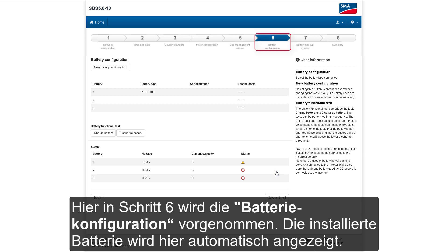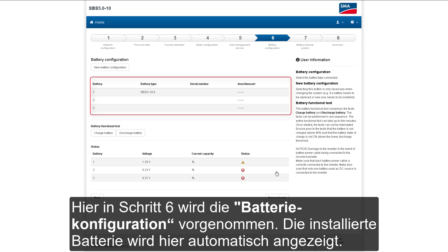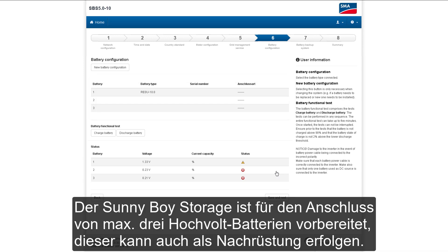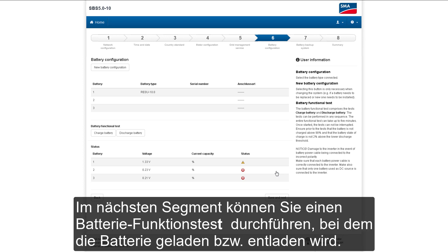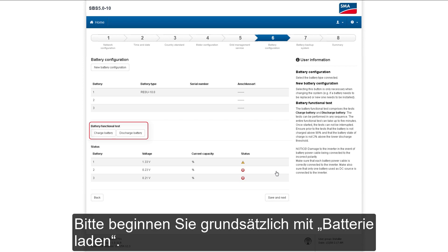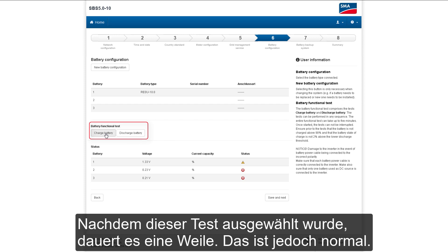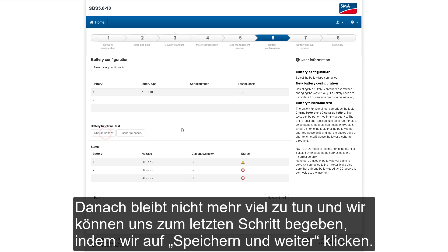At step six, we can set the battery configuration. The installed battery will be shown here automatically. The Sunny Boy Storage is already prepared for the connection of up to three high-voltage batteries, even as a retrofit. In the next segment, you can perform a battery function test in which the battery is charged or discharged. Please always start with charge battery. Once we click that, it takes a little while to perform the test, but that's quite normal. After that, we can go on to the final step by clicking Save and Next.